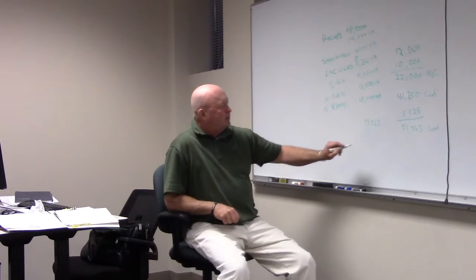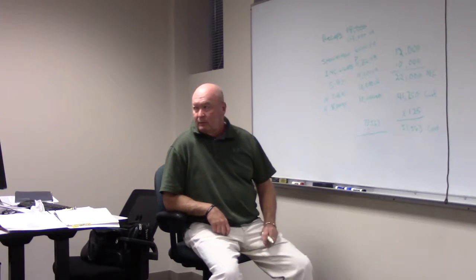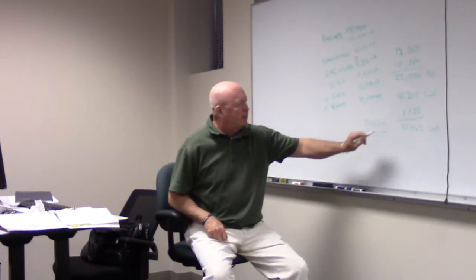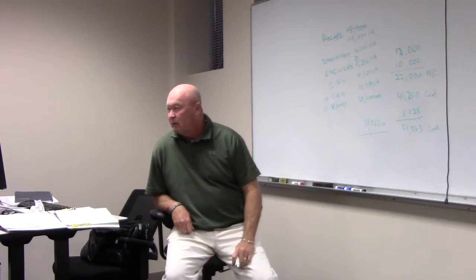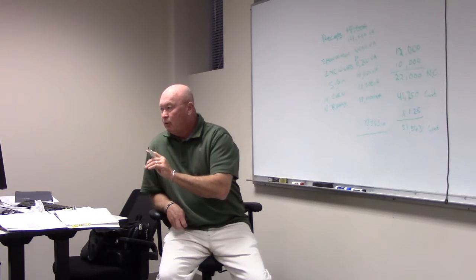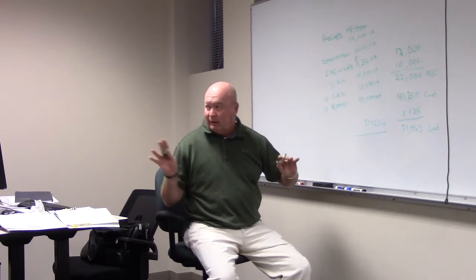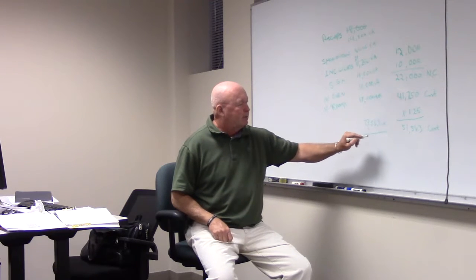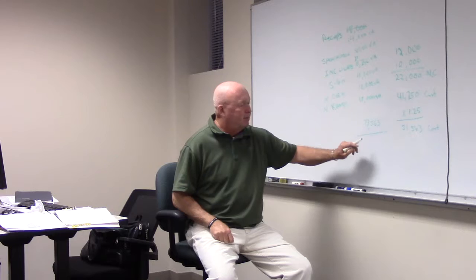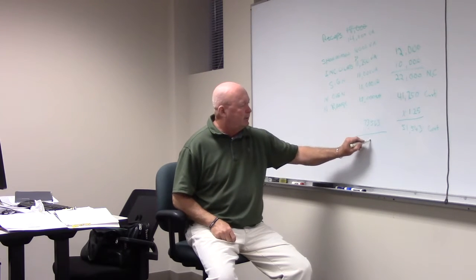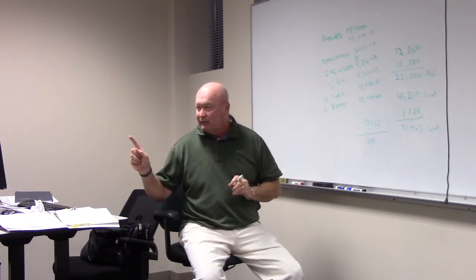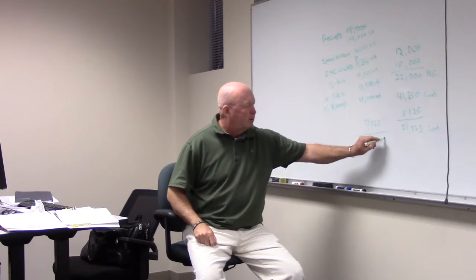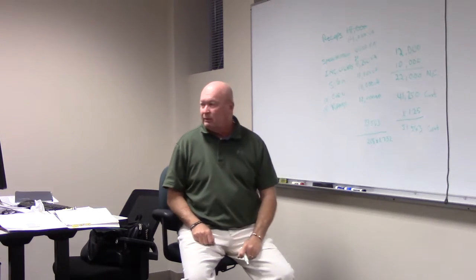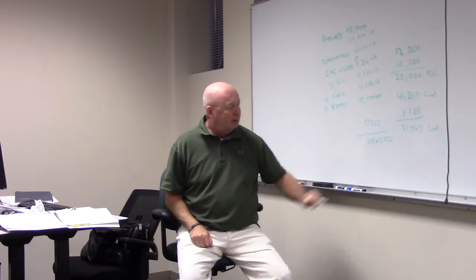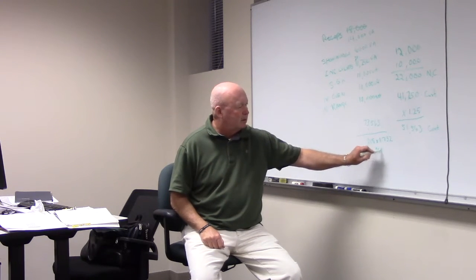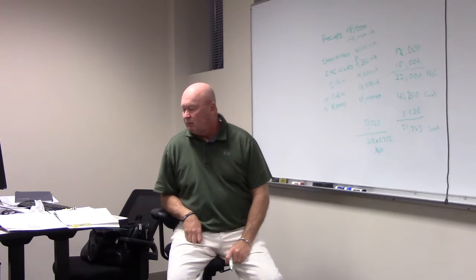So what's our 208? This is watts, or VA. That's our total load right now for 208. Yes. But we said it's 208, three phase. So normally, if it was single phase, we'd take 73 thousand VA or watts and divide it by the voltage, wouldn't we? Which would be 208, right? Yes. But because it's three phase, we have to multiply that times 1.732, which should give us like 360, close to it. See if you agree with me.